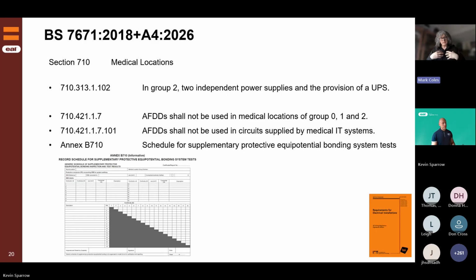So in that area you've got probes into the patient, and when you're under the knife, the last thing you want is the power supply to go out. So in Group 2 locations, two independent power supplies are necessary coming into that area. If you lose one bank of sockets, there's another bank where the surgeon and their team can plug equipment in. But there also needs to be provision of a UPS, an uninterruptible power supply. That's been clarified, and it's really important.